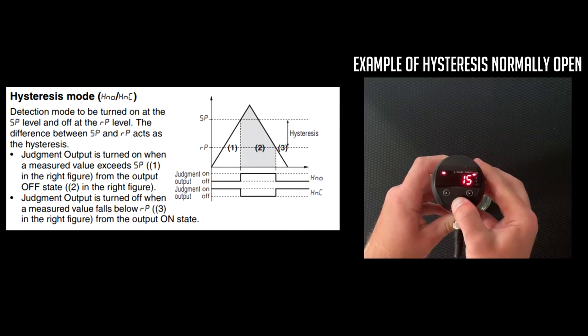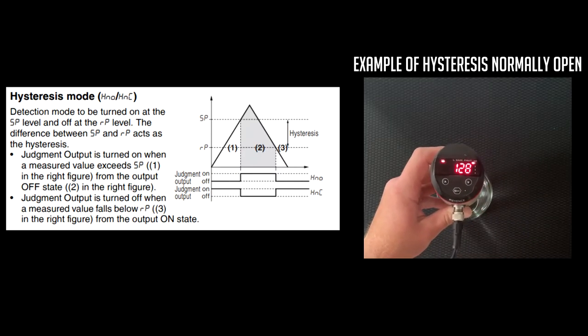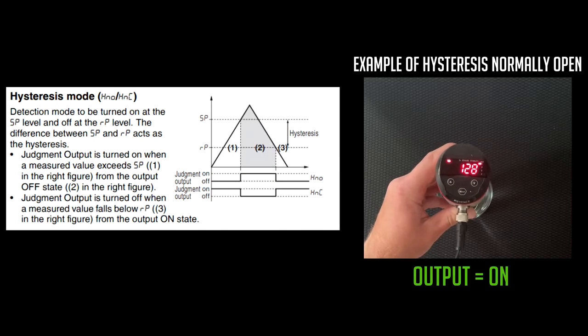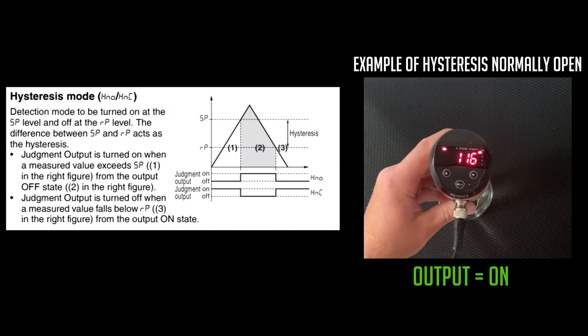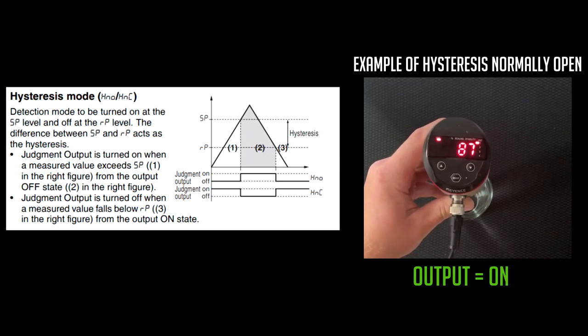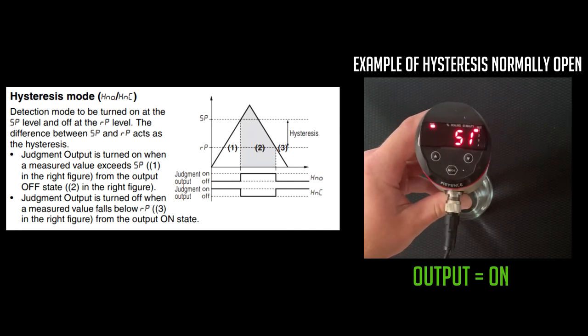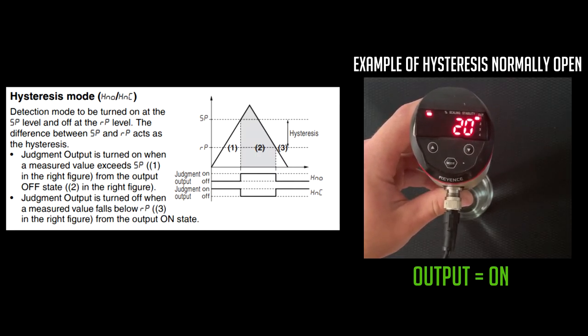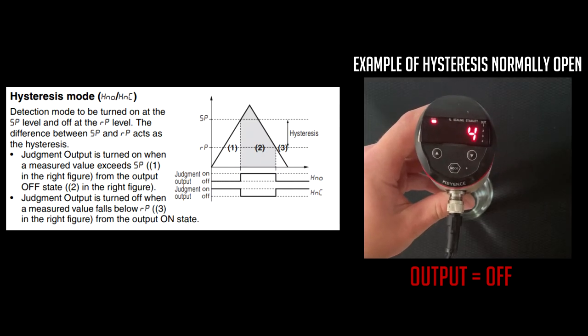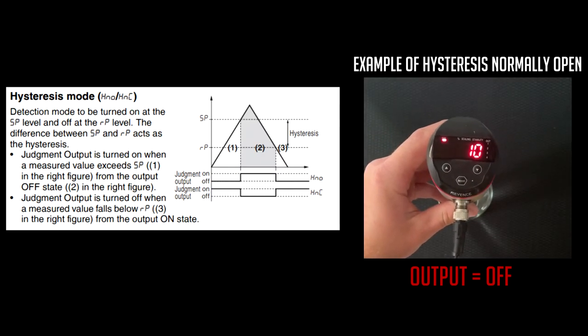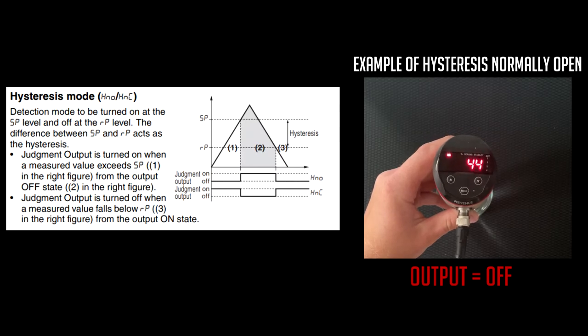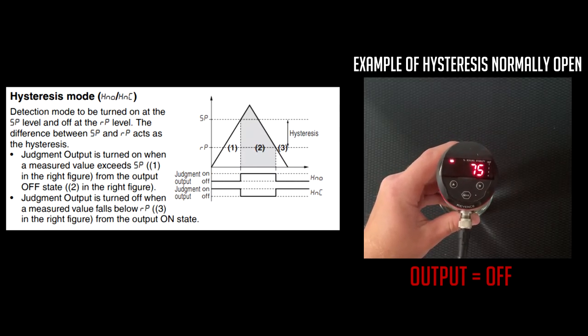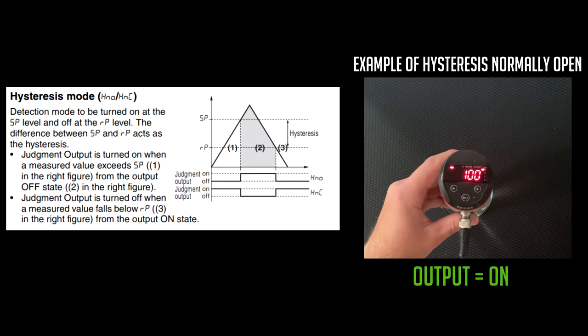So now I have set my SP1 as 100, and my RP1 as 15. So as we go through this example, we see that since we're above 100, our output is on, and as that number drops all the way to our RP1 level of 15, our output would then turn off. And that output will not turn back on until we hit that SP1, or set point 1 level again, right here.